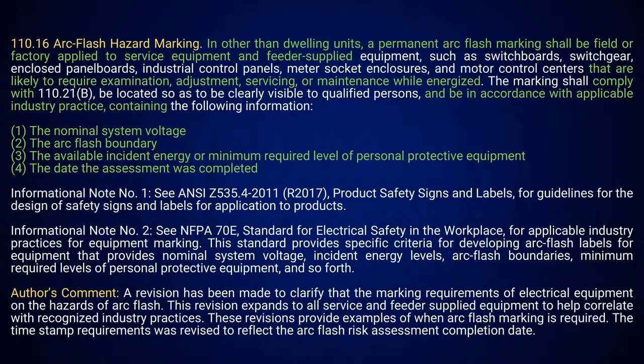I'm going to try to expand on that more. I did kind of open some eyes about that, and that was cool because with those VAB units, you could energize the hell out of them, and you have to shut that switch off to open them. There's no arc flash hazard present with those in the open position because everything in the working space is de-energized. The only thing still energized is the terminals behind a barrier, so we actually examine that pretty closely.